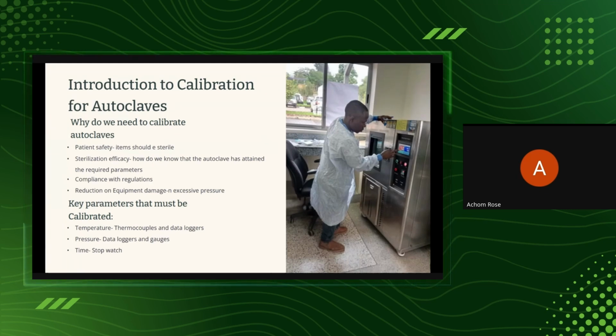Okay. Two, sterilization efficacy. How do we know that the autoclave has attained, we talk of 121? I think the most common for sterilizing instruments is 121 degrees Celsius. How do we know that the equipment has actually attained 121 degrees Celsius? Okay. If it is supposed to be at a certain pressure, how do we know that this pressure has been attained and the sterilization process has actually started? All right. The third one is compliance with regulations. We all have regulations in our respective countries. So this calibration also helps us to follow and comply with these regulations.